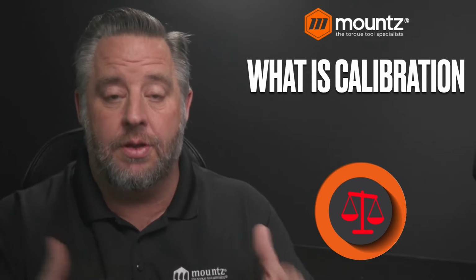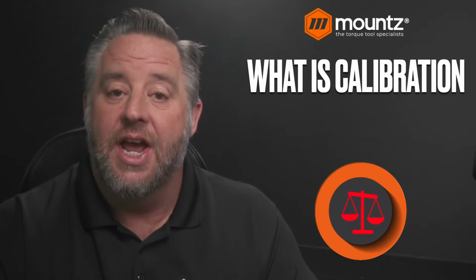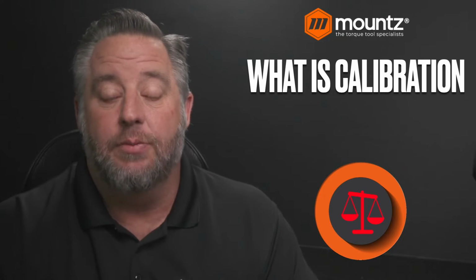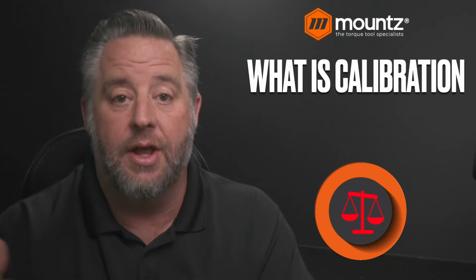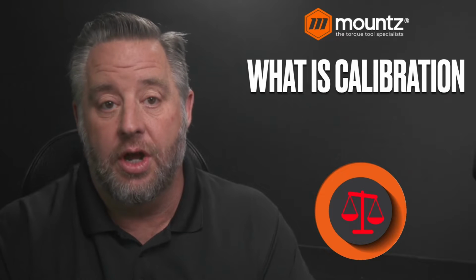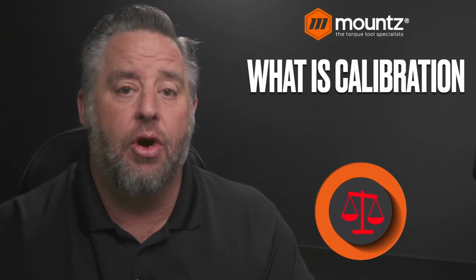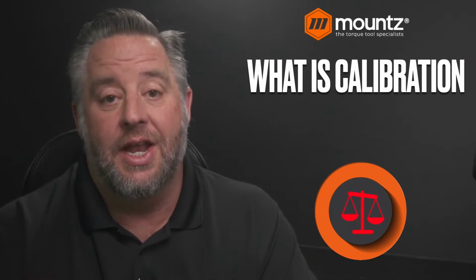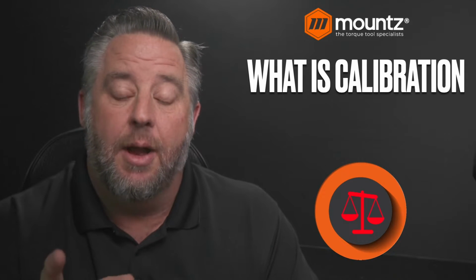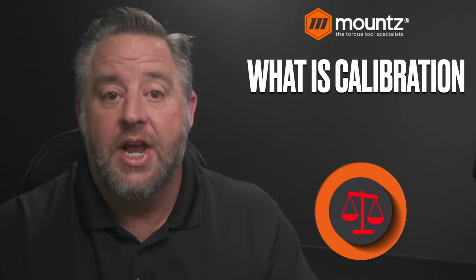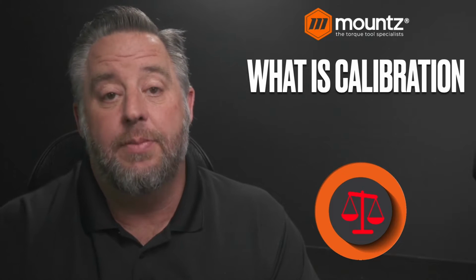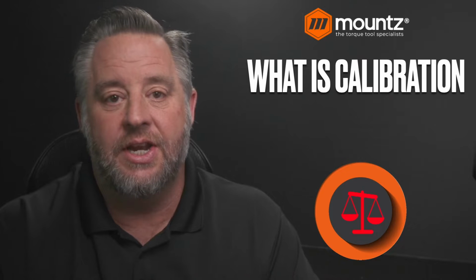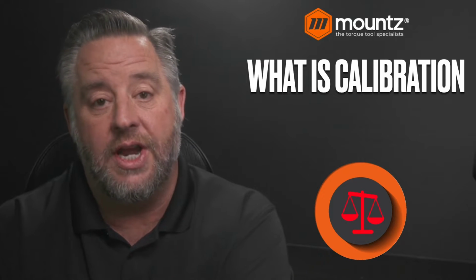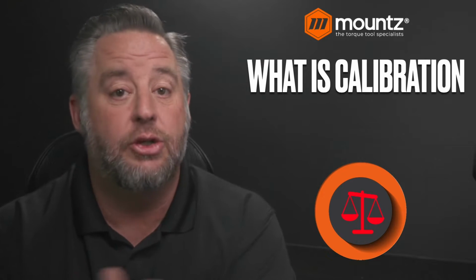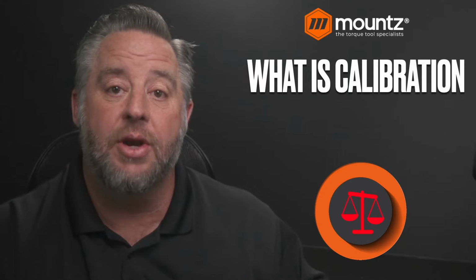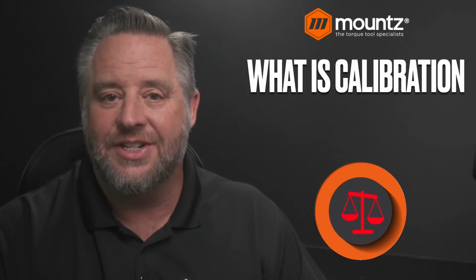When we talk about calibration purposes for tools or for sensors, we might want to define what calibration is. Calibration is typically measuring our tools with the use of a higher accuracy level of tool. These are all part of any type of ISO specification or NIST standard or an international standard as well. Calibration allows for traceability through the process and also helps to gauge any type of uncertainty that we might find. All of this is encompassed in the actual calibration process, from the very beginning of the traceability to the final result of a torque tool that is being calibrated. In this case, we're talking about torque sensors. So let's keep on going with that.